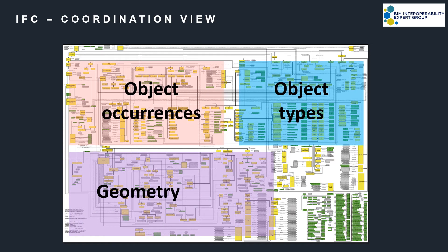Very roughly speaking, it breaks down like this. Because this doesn't change, I can build rules which will tell me if a door will clash with a light fitting, or to ignore pipes below 20mm when conducting clash analysis. I can also check the data side — for example, that all objects follow the project's naming convention and that the property flow rate is filled in for all chillers.